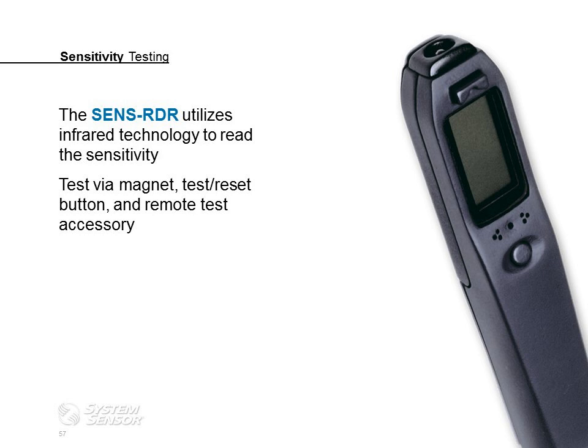You can take this to the remote test accessory, that RTS2 or RTS2AOS, and point it at the spot you'll see molded into the housing where you place the sensitivity reader. You push the button, and it will actually give you a true obscuration per foot sensitivity reading, as well as a textual message that says good, service, or replace.